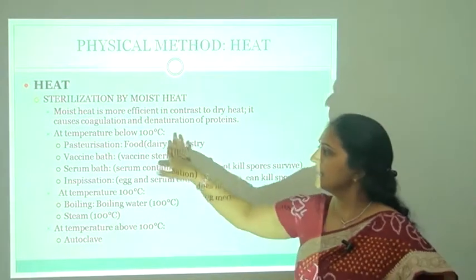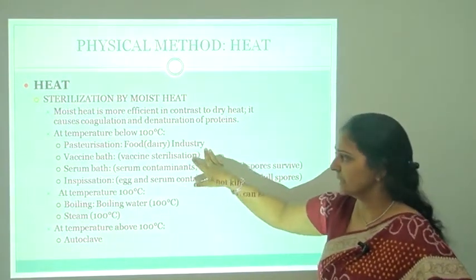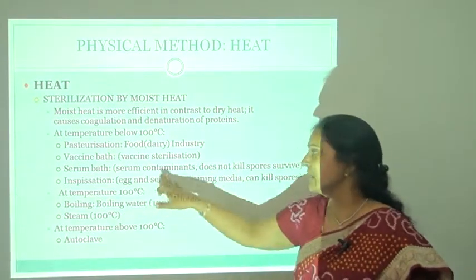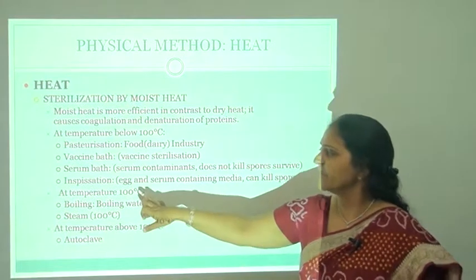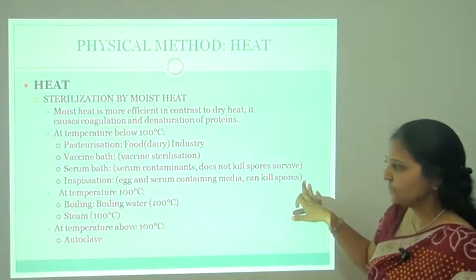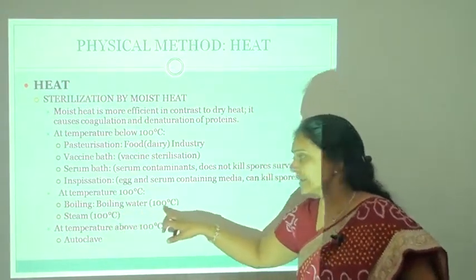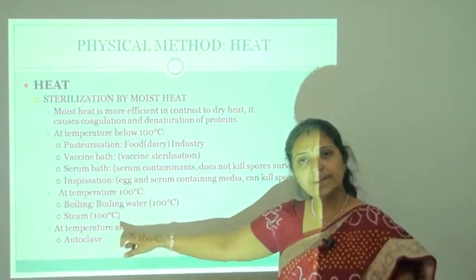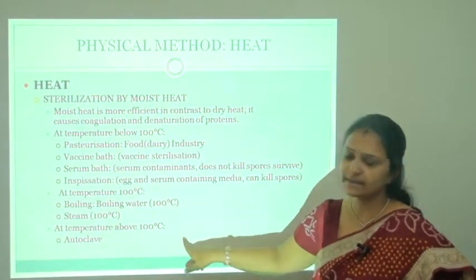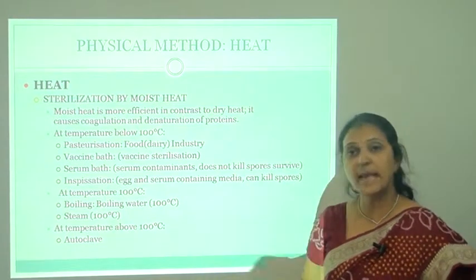At temperatures below 100°C, methods include pasteurization (used in the dairy industry), vaccine bath for sterilization of vaccines, serum bath for sterilization of serum, and inspissation for egg and serum-containing media which can kill spores. At 100°C, methods include boiling water and steam. At temperatures above 100°C is the autoclave, which operates at 121°C and 15 LB pressure using steam under pressure.